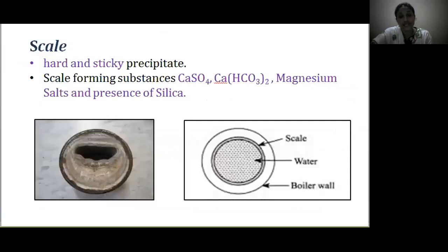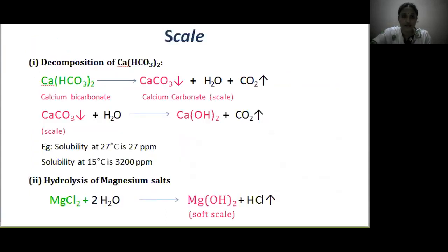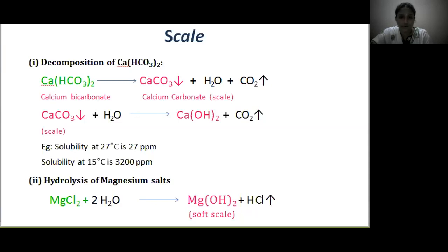What are scales? Scales are hard and sticky precipitates firmly attached to the side walls of the boiler. Scale-forming substances include calcium sulphate, calcium bicarbonate, magnesium salts, and silica. One reason for scale formation is decomposition of calcium bicarbonate: it decomposes into insoluble calcium carbonate and deposits as loose scale, causing problems in low-pressure boilers. In high-pressure boilers, these compounds are insoluble at high temperature, also creating problems.